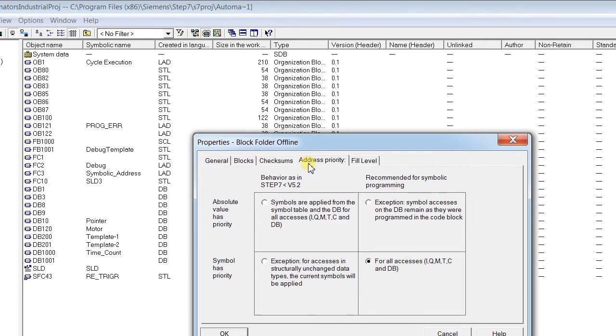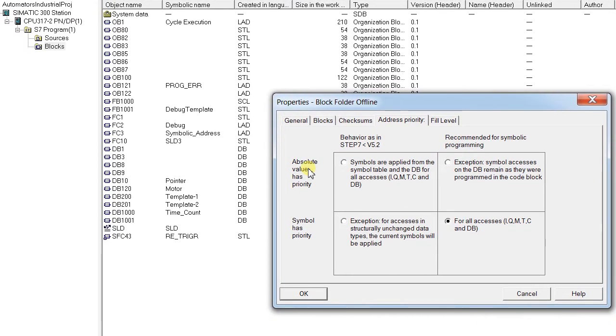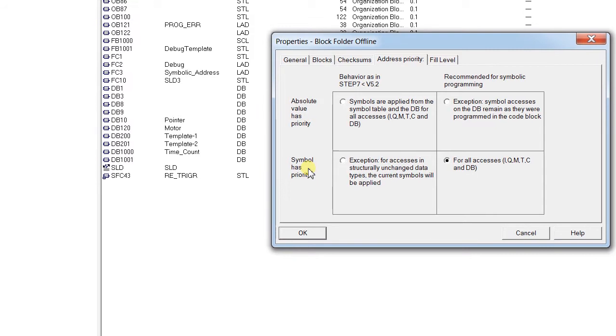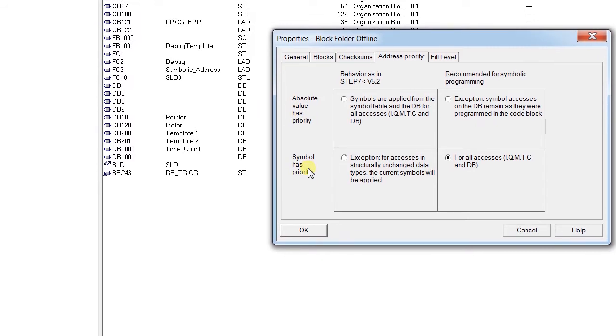Under Address Priority, you can see the options: 'Absolute value has priority' and 'Symbol has priority.' Most beginners make the mistake of going with absolute value as priority. My suggestion is that absolute addressing is not intended — the logic is not maintained throughout when the addressing is changed. It is always preferable to go with symbolic priority.